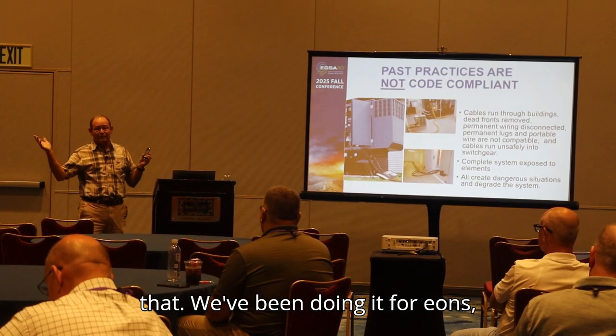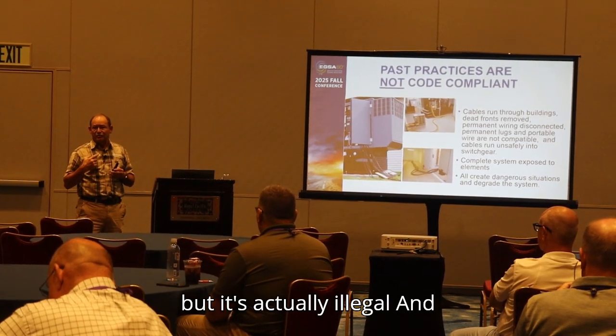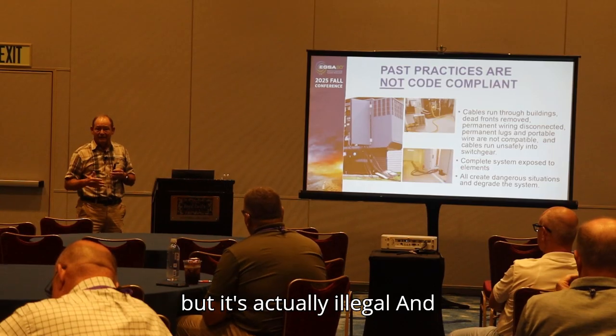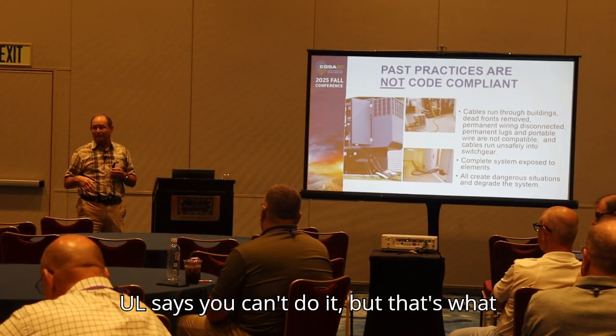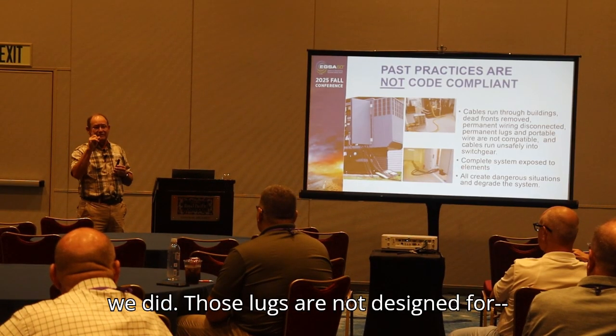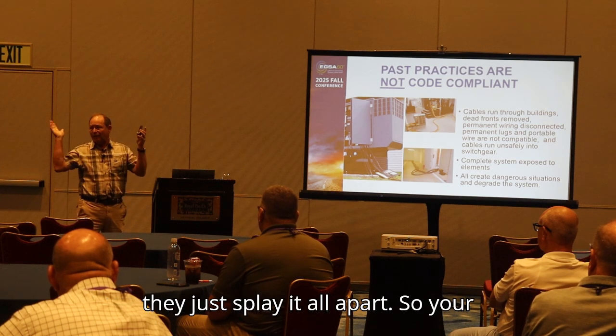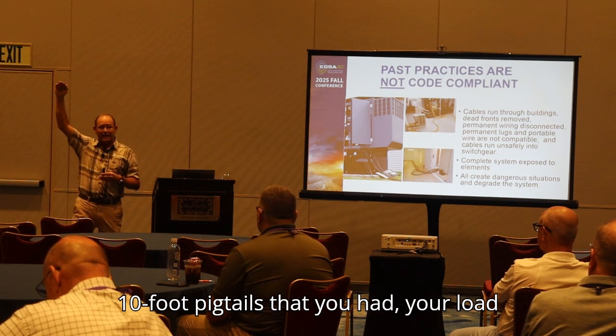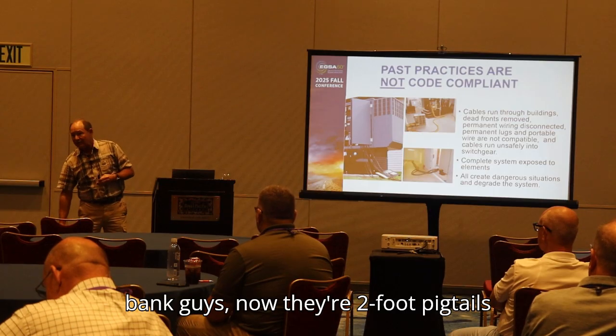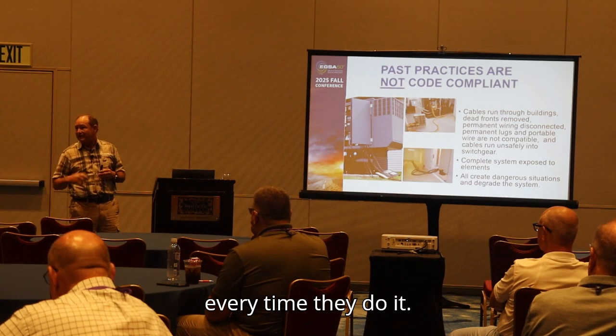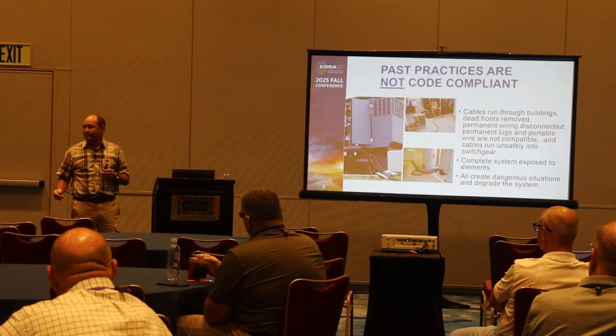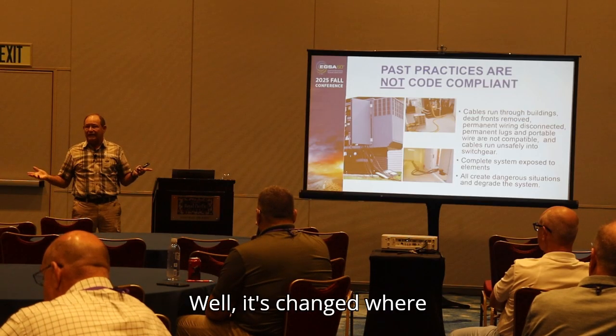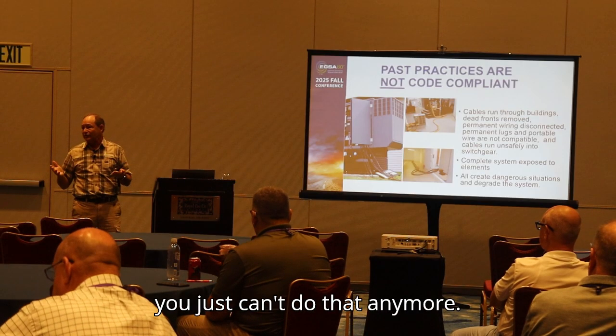You can't even do that. We've been doing it for eons, but it's actually illegal, and UL says you can't do it, but that's what we did. Those lugs aren't designed for that, they just splay it all apart. So your 10-foot pigtails that the load bank guys had are now 2-foot pigtails because they have to whack them off every time they do it. It's changed, you just can't do that anymore.